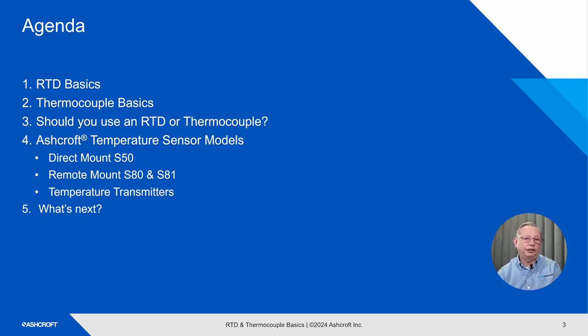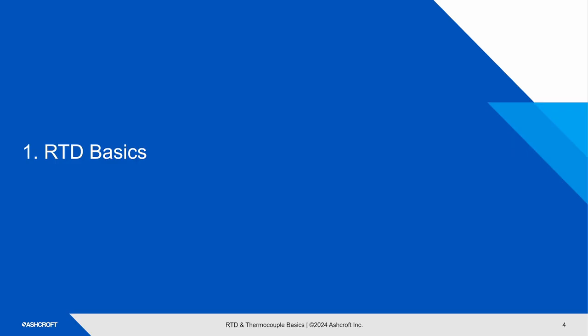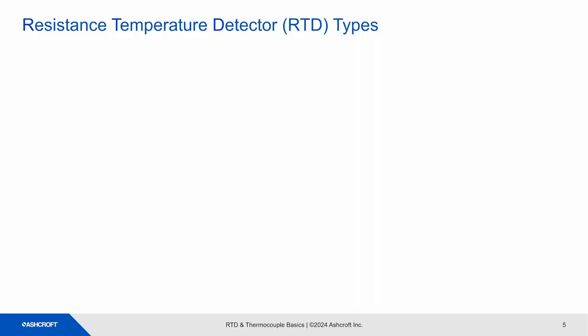Should you use an RTD or thermocouple? Ashcroft's temperature sensor models, the direct mount S50, the remote mount S80 and 81, temperature transmitters, and lastly, what's next? Let's start with RTD basics. RTDs are resistance temperature detector types.